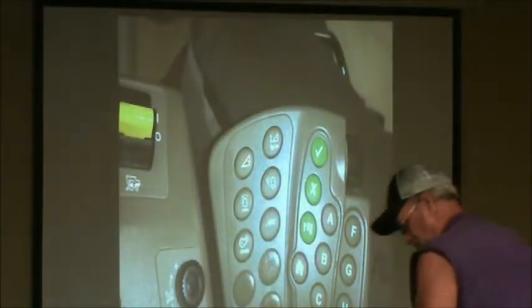This button here on your armrest is going to be our draper speed. If you push that button on your armrest, it looks like the head. You push it once and it's going to pop up and say hydroflex pressure right here on number 1. And you'll either have the plus and the minus, or on the side the dial. You can adjust that pressure on your hydroflex up or down, however you need to go.